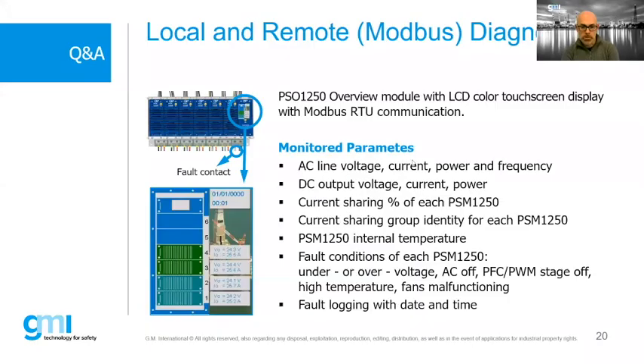And I wanted to remember that the diagnostic is very important to reach a higher SIL level, especially in applications such as fire and gas or energize to safe applications. If you have a monitoring system, the undetected dangerous failures can be reported, transformed into detected failures, because the diagnostic will transfer this information to your system, and in this case you can know what's happening. If you know, the failure will be detected; if you don't know, it will be undetected. That is very bad for your safety application.